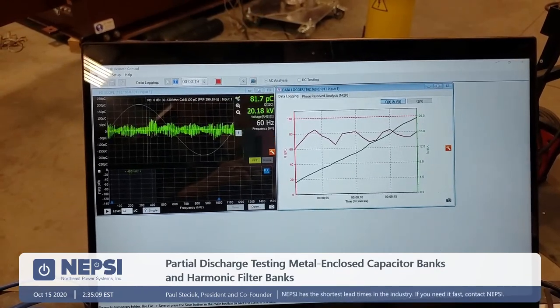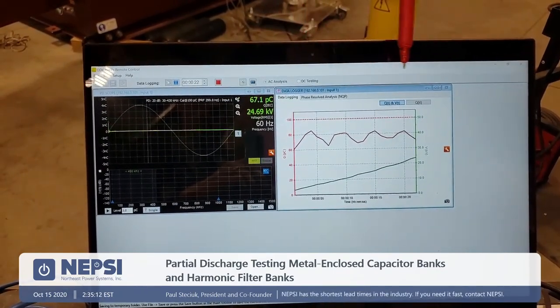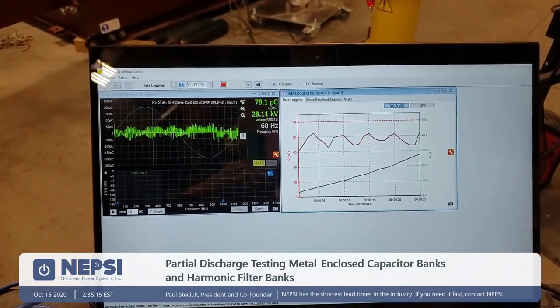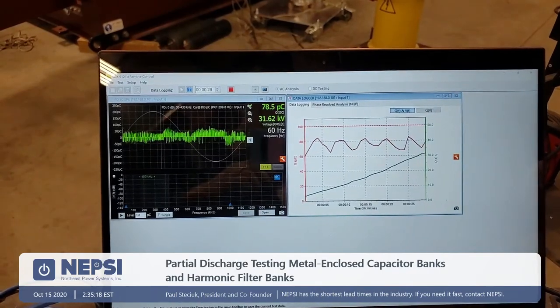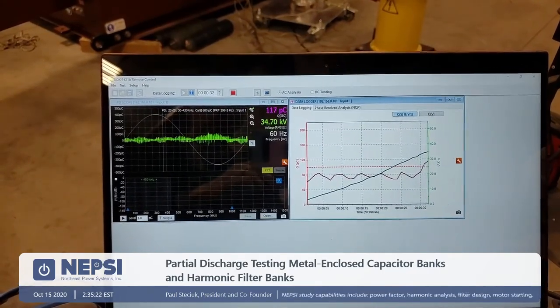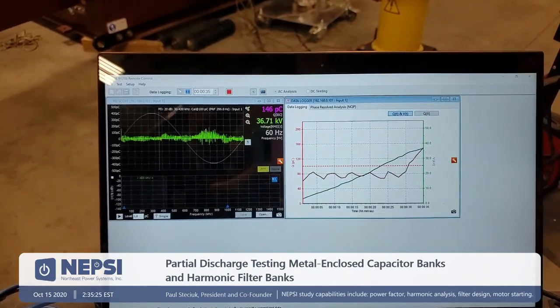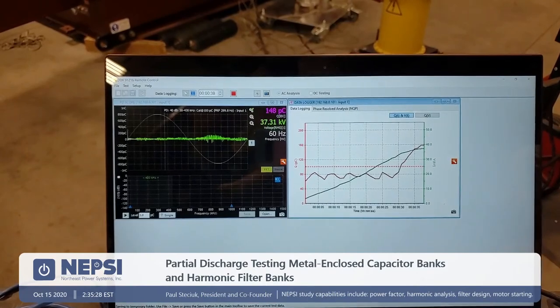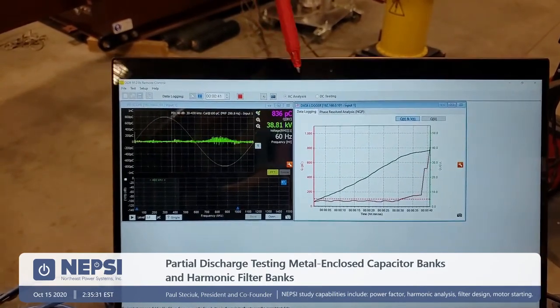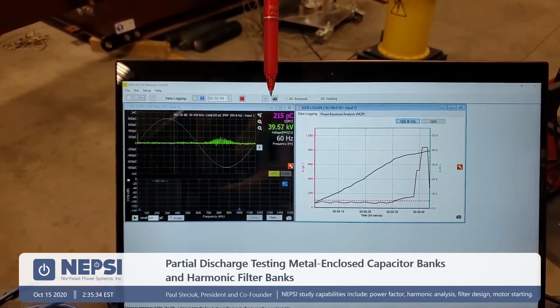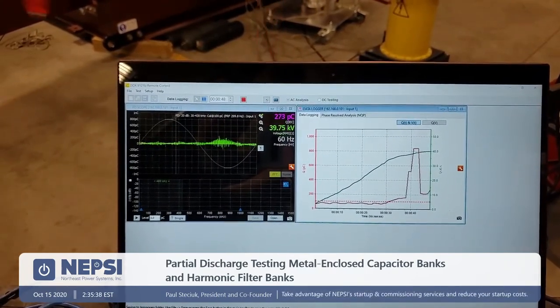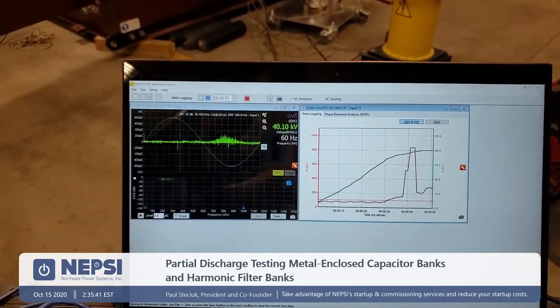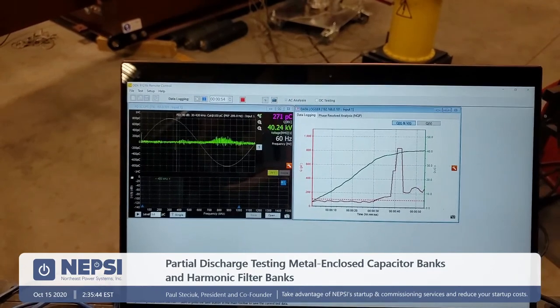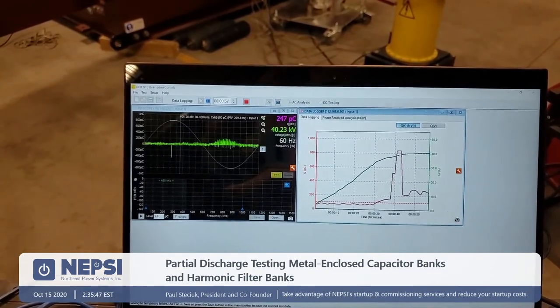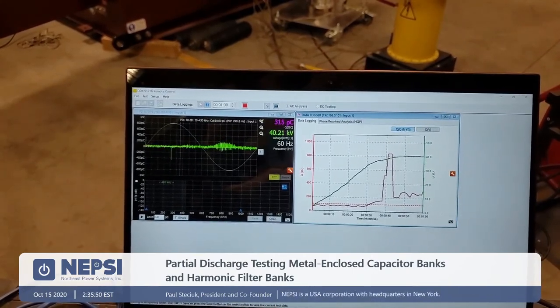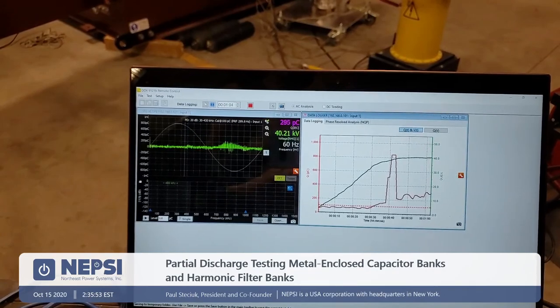17 kV, 20 kV. The plot to the right is picocoulombs and voltage versus time. So it's recording kV for the entire test that's going on here. 35 kV, and we just hit above the 100 picocoulomb value, Paul. All right, so you're at 38 kV. You can see where we're bouncing very high up in picocoulombs now, indicating that we are into a partial discharge area. 39.8, 40. All right, so we're at 40 kV, and this would be an indication that we are beyond the corona inception voltage, which is something lower than where we are here.